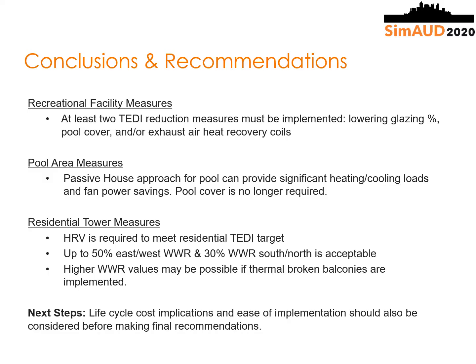Here are the conclusions and recommendations for this analysis. First, we looked at lowering the glazing percentage, adding the pool cover, and adding exhaust air heat recovery coils to the recreational facility. Since none of these can reduce the TEDI enough to meet the project targets, we recommend at least implementing 2 of them. For the pool area, we looked at a passive house approach and found that it can provide significant heating and cooling loads and fan power savings. And also the pool cover is no longer required with this approach.